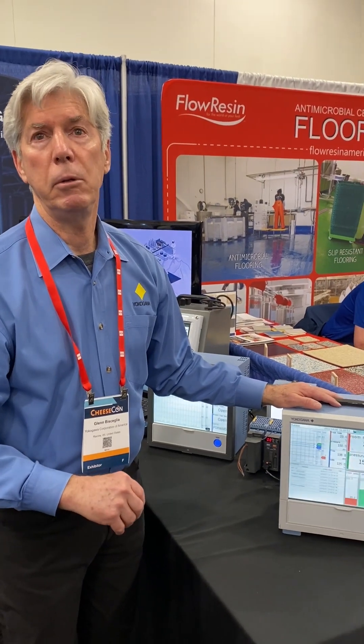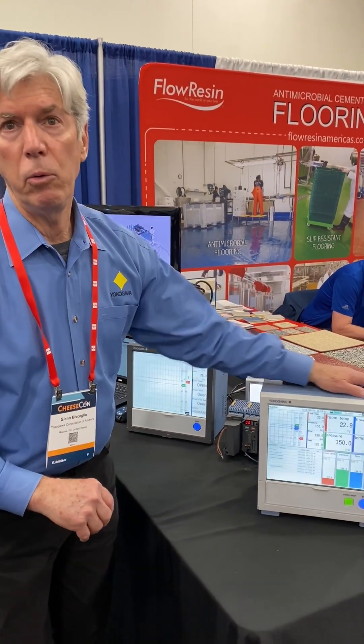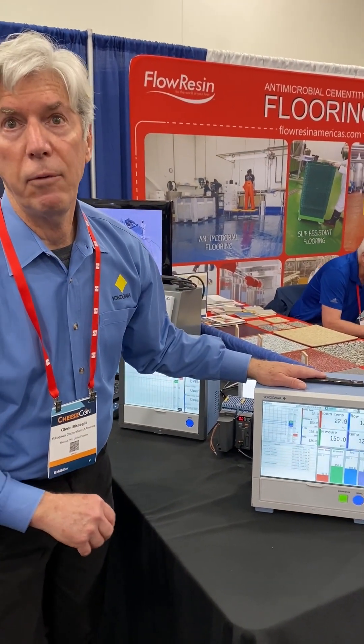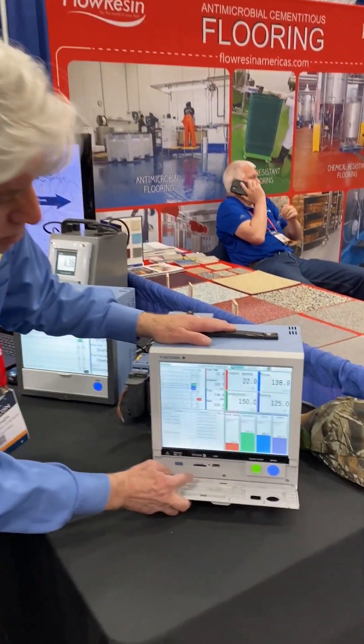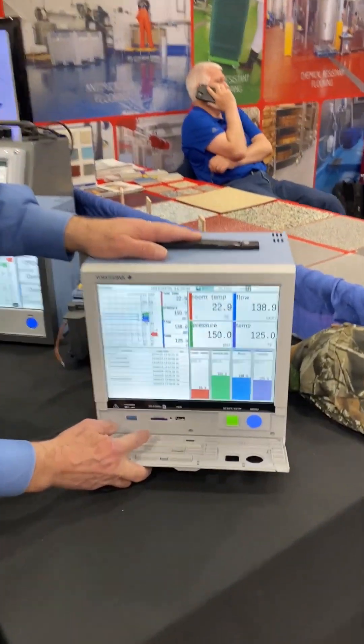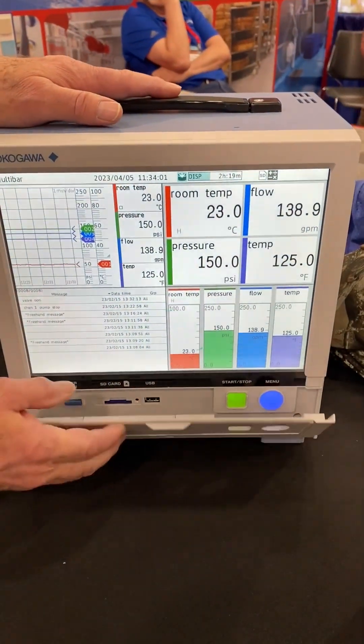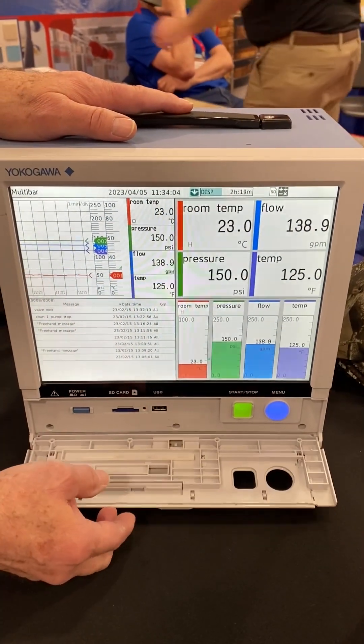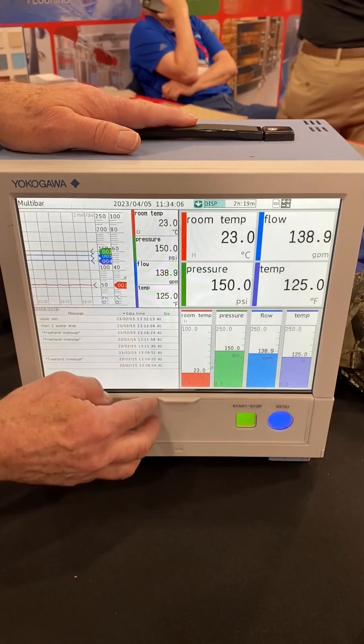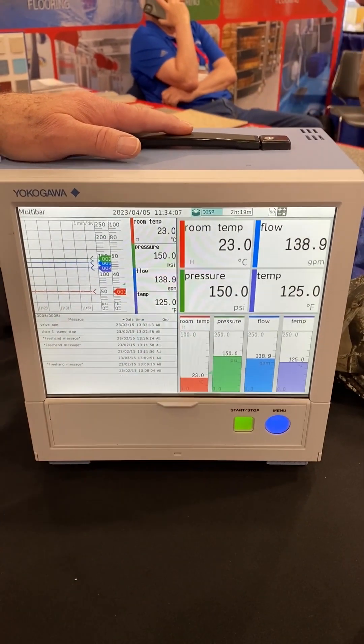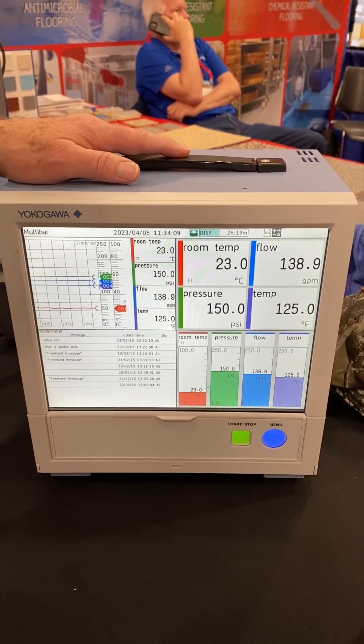It becomes part of a secure encrypted database that's stored both in the internal non-volatile RAM as well as on a removable SD card media. There's a 32 gig media in there. If 20 channels are logging every second, that media would fill every eight years.